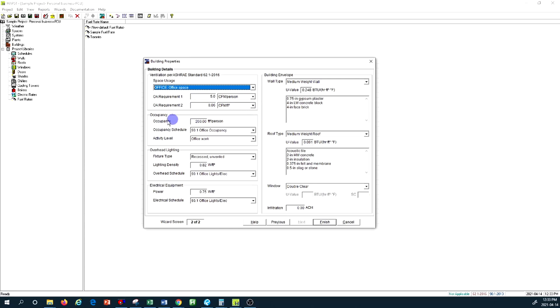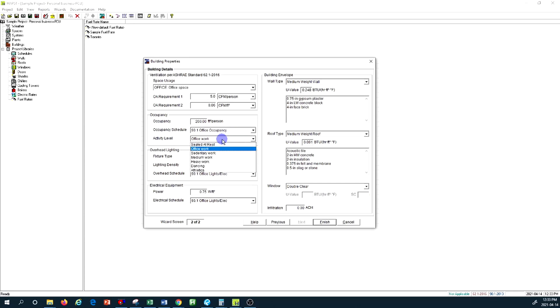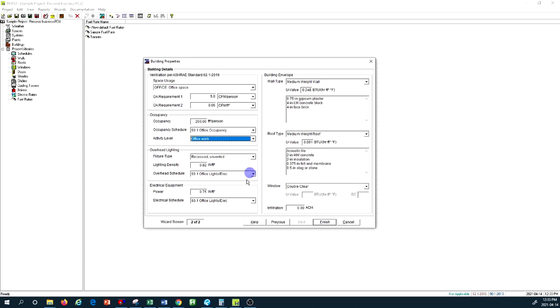As you know from the ASHRAE Standard 62.1, automatically the calculation takes place for that type of occupancy for the entire building's fresh air requirement. I'm not going to change anything here. Occupancy you can keep it as 200 square feet per person. For the occupancy schedule, we want it to be occupied during office hours. The level of activity, there are all types of options but this is office work, I keep it as is.